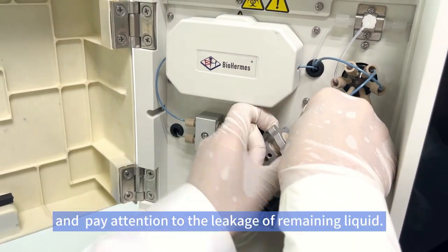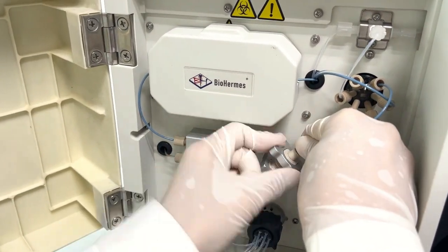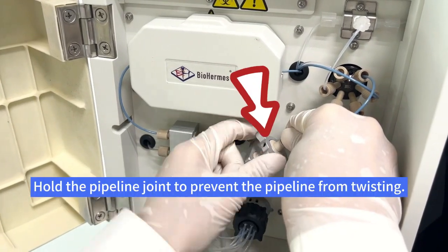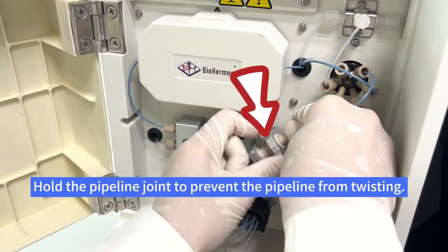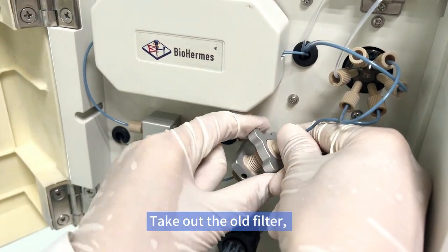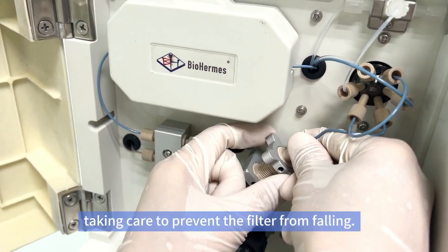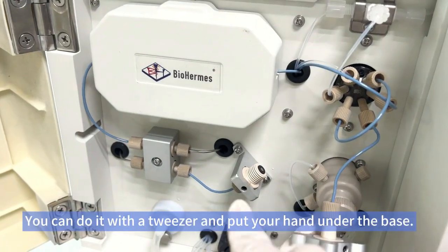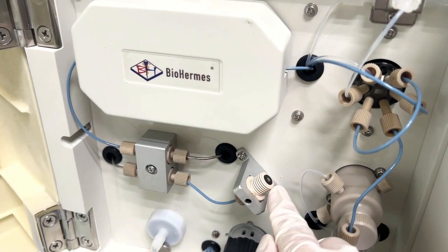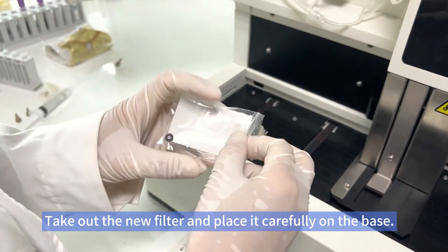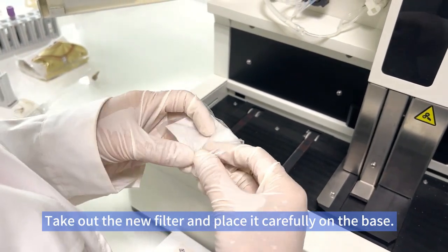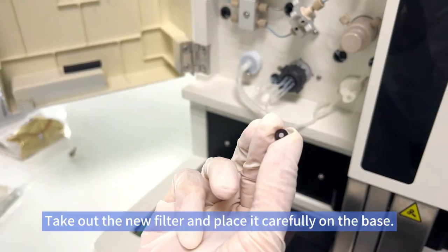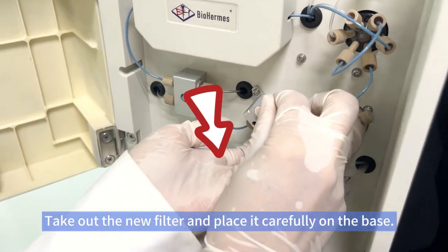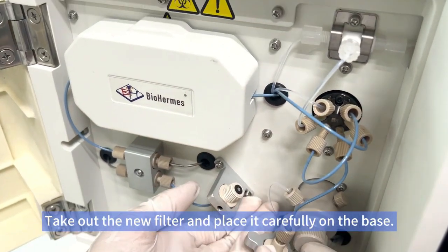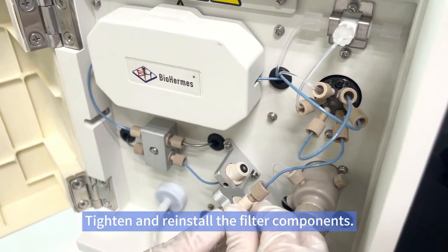Filter replacement. Carefully unscrew the filter components, and pay attention to the leakage of remaining liquid. Take out the old filter, taking care to prevent the filter from falling. You can do it with a tweezer and put your hand under the base. Take out the new filter and place it carefully on the base. Tighten and reinstall the filter components.